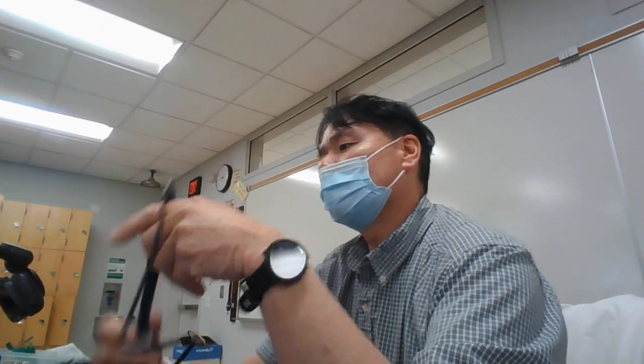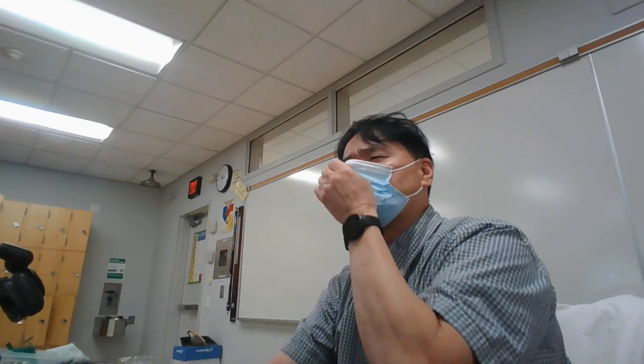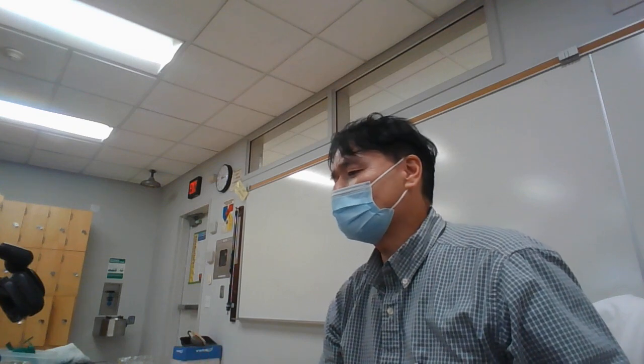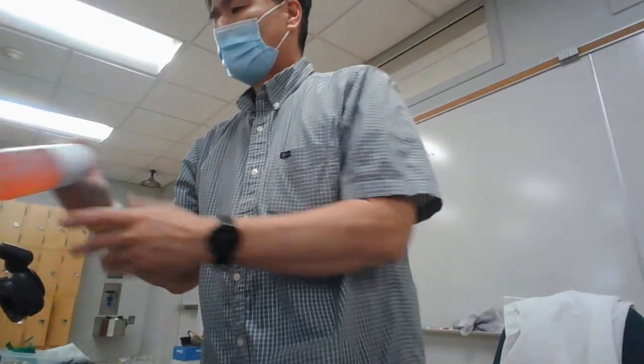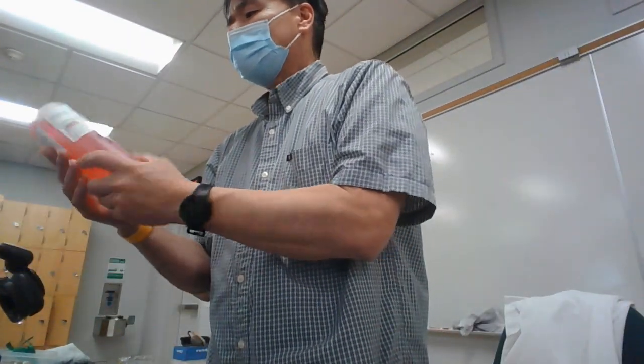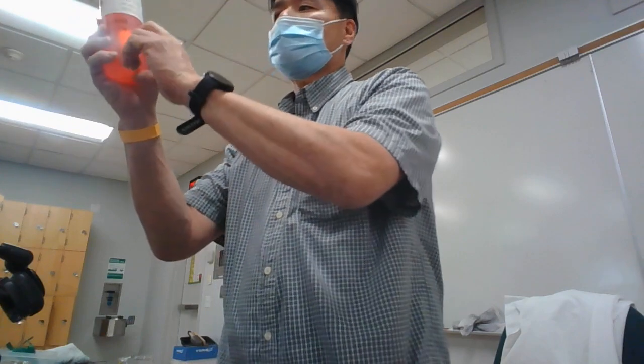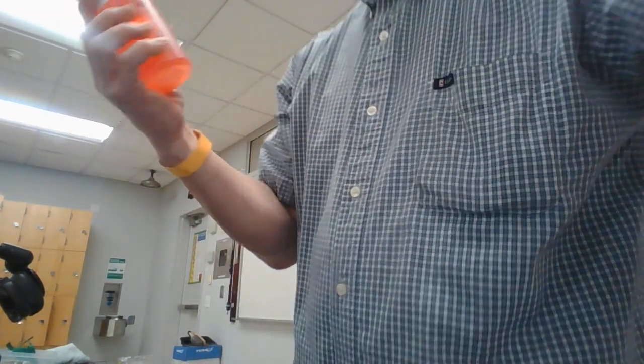And we don't. And so what we do normally as a first step is something called a calibration to make sure it's reading correctly. But before we do the calibration, let's just go ahead and try to measure the pH of something that we know what the pH is. And we're going to measure the pH of these solutions. We have this one here and this red one and the green one.